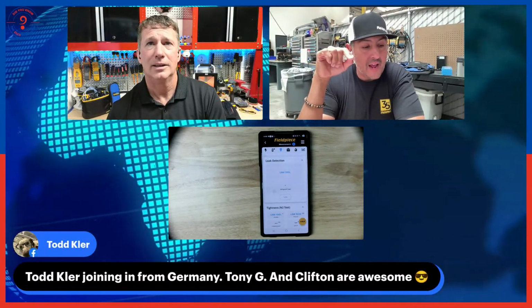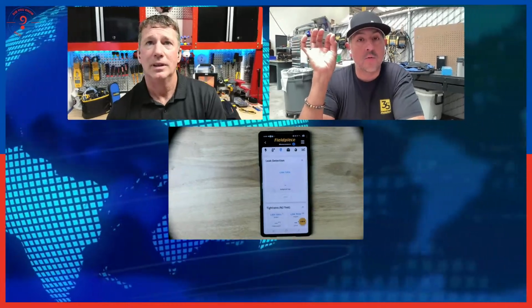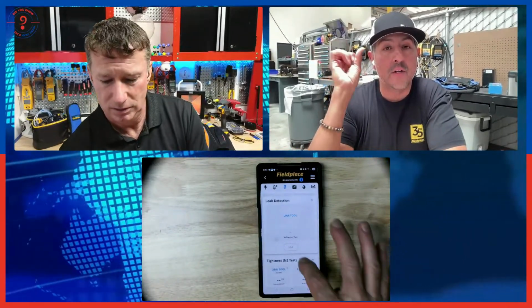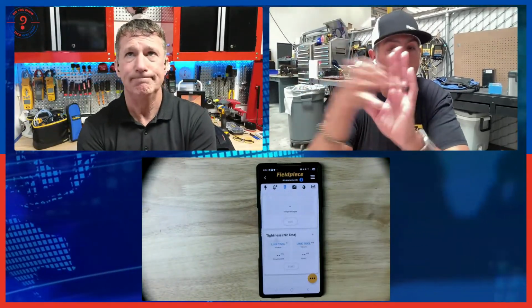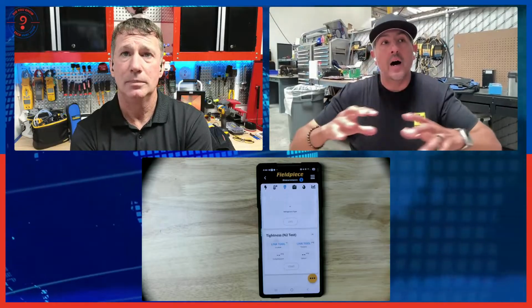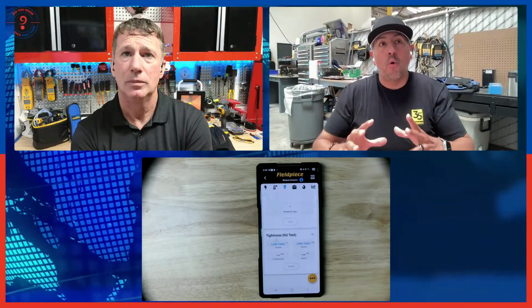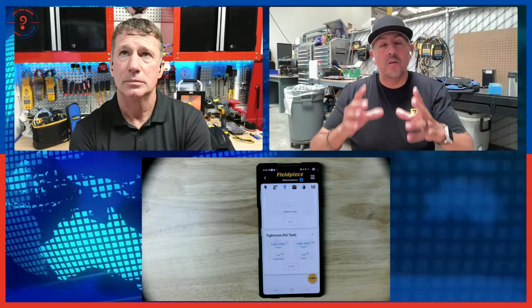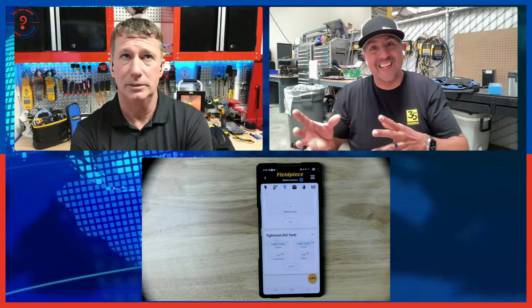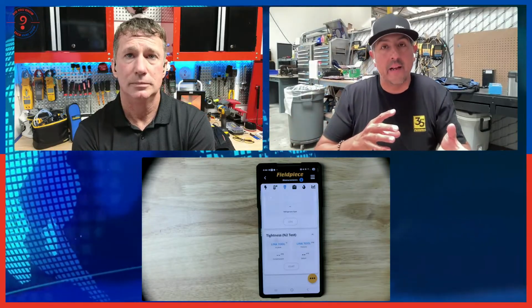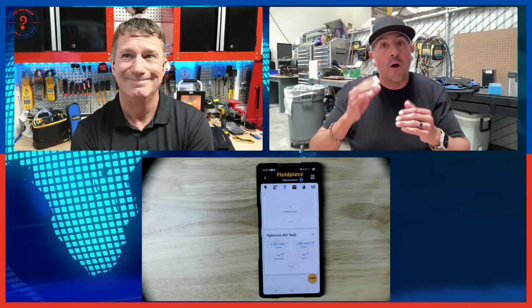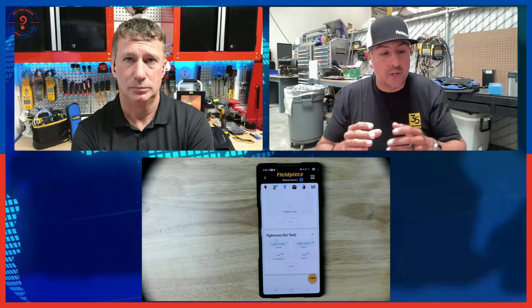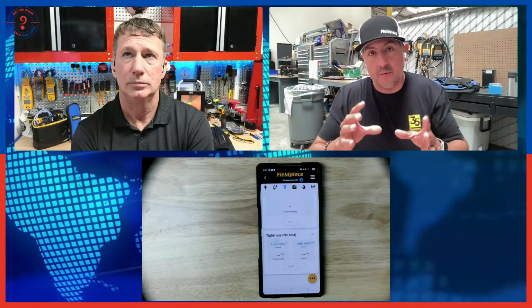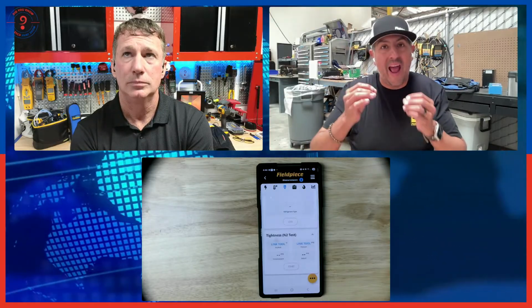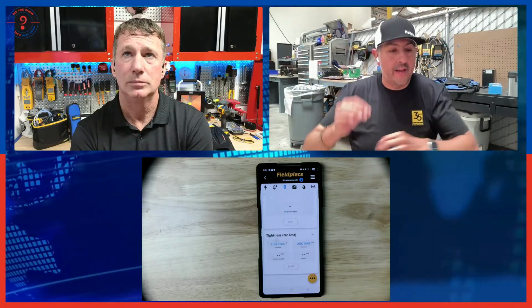And then at the bottom of that, there's a tightness test. That's also relatively new, that you can use either your SMAN digital manifold or your Job Link probes to perform, record, time, and document your nitrogen pressure test, right? Absolutely. And the nice thing is that it is temperature compensated. If there are changes in pressure due to temperature, the app will take that into consideration and calculate it to make sure that you get a more accurate pressure test, okay?